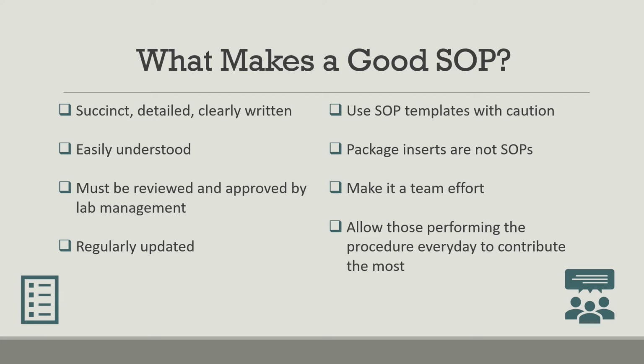Writing procedures really should be a team effort, and those that are performing this procedure daily should be encouraged to contribute since they are most familiar with the testing process. Also, again, package inserts are not SOPs. However, these can be incredibly helpful for writing your procedures. They do lack laboratory-specific information, and that's something that you would need to add in your procedure. Information and illustrations from package inserts can also be included in your procedure, especially illustrations can be very helpful.